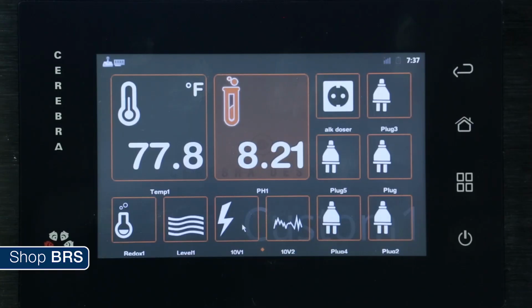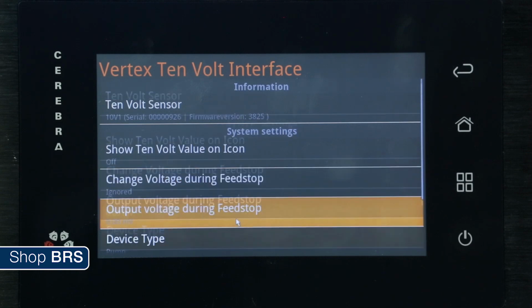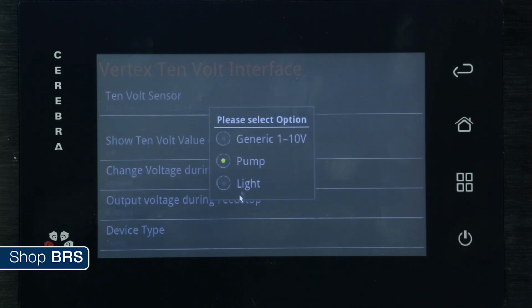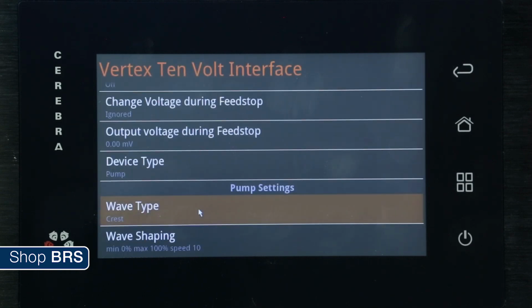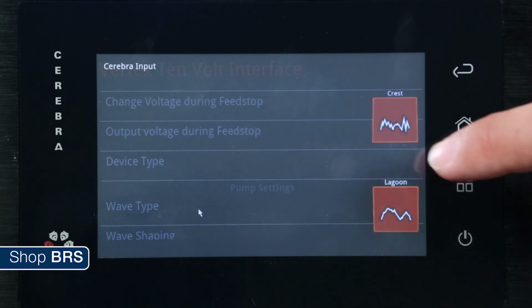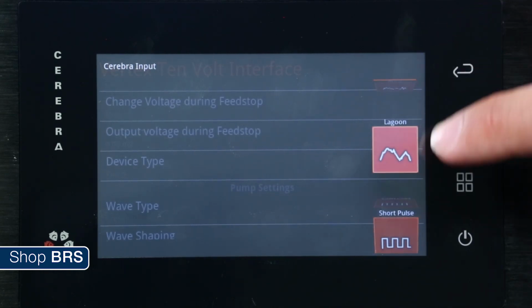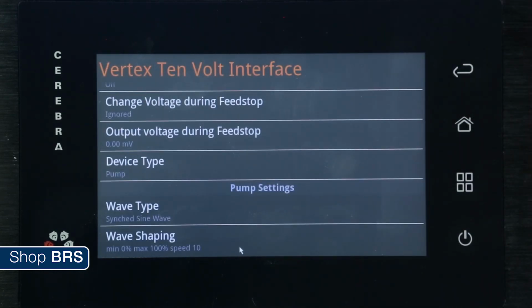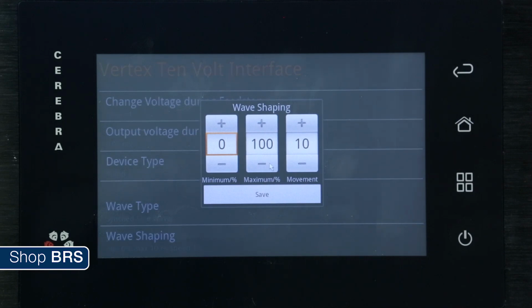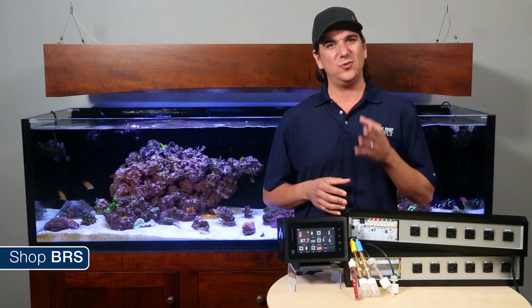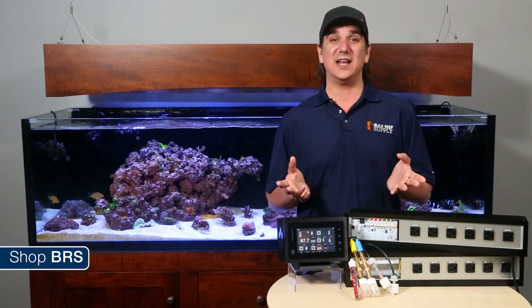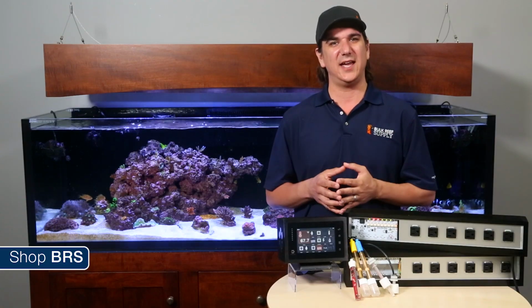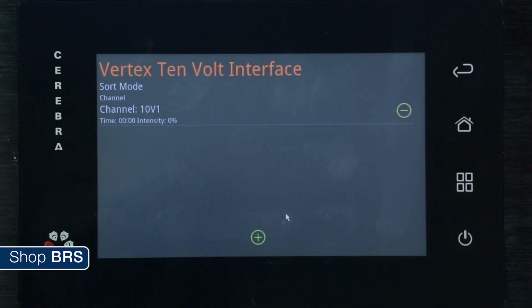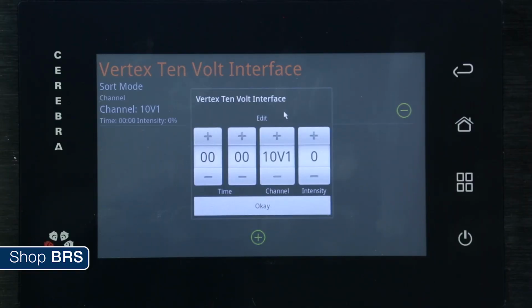Notice there are also 0 to 10 volt inputs to control lights and power heads. Click on the icon, device type pump, then wave type, and select from all kinds of waveforms for your power heads, which you can use on any 0 to 10 volt pump. Then under wave shaping, select the max and min speeds for your pump. Just simple and easy. One more thing I think anyone can do without a single set of instructions and right at the tank. Lighting programs are similar, but you can just add intensity points based on the time of day.